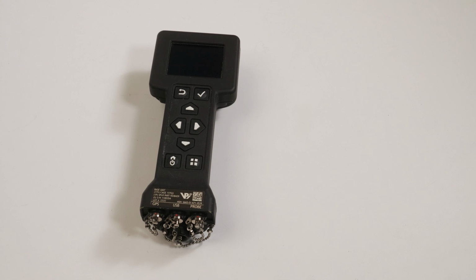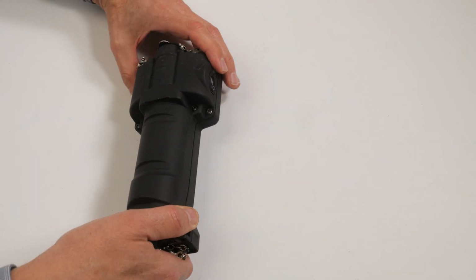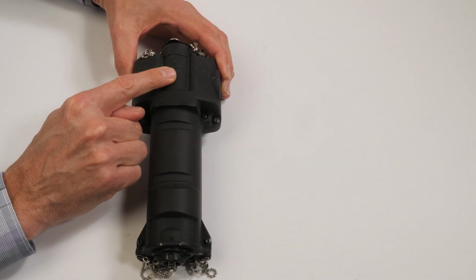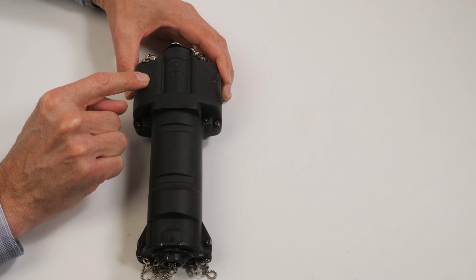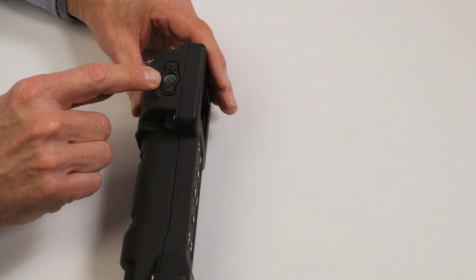The back housing has detector center marks to show the location of the low-dose Geiger-Müller tube and the high-dose GM tube. These will come into play when we do a source check. Note that the speaker port is on the left side.